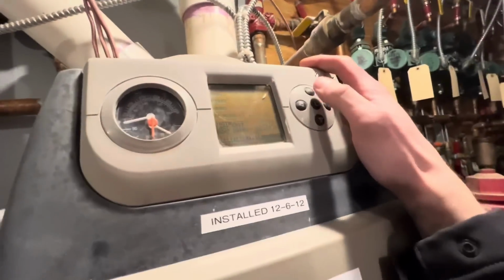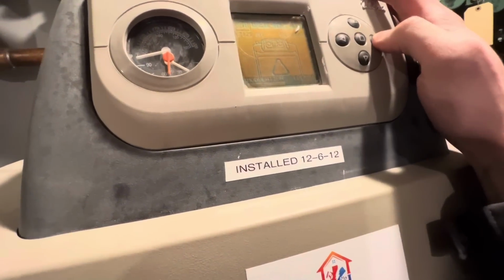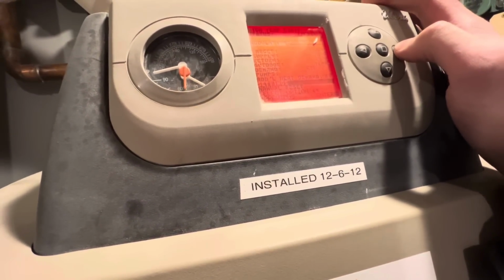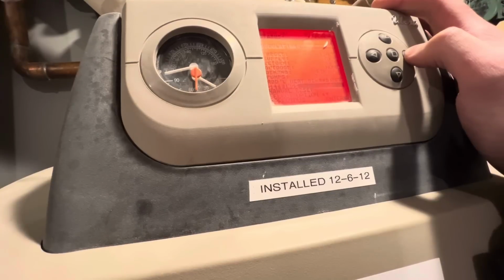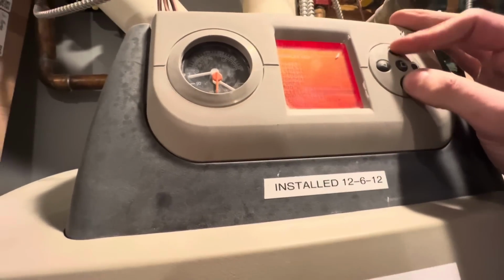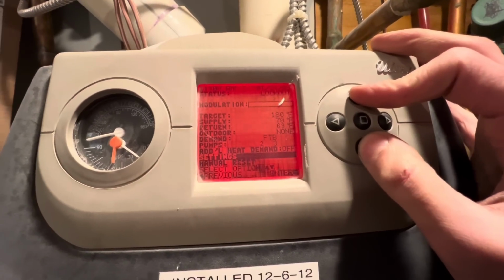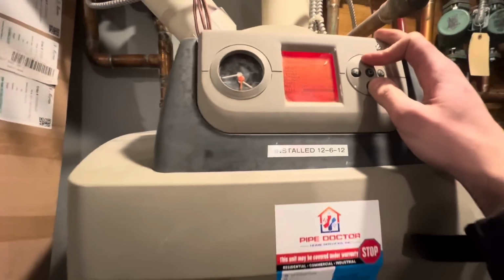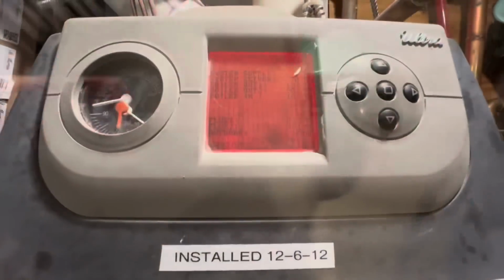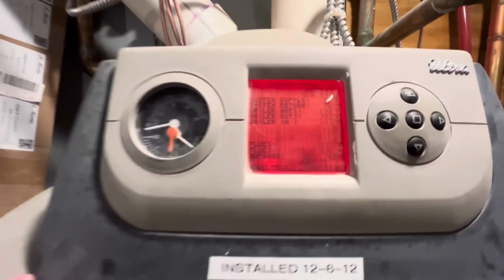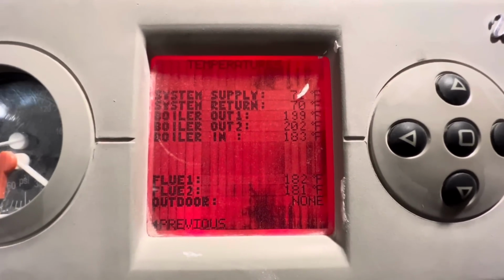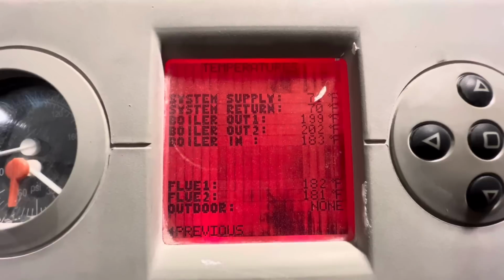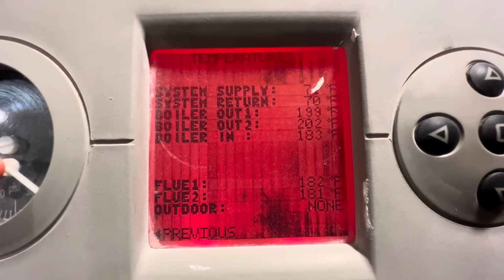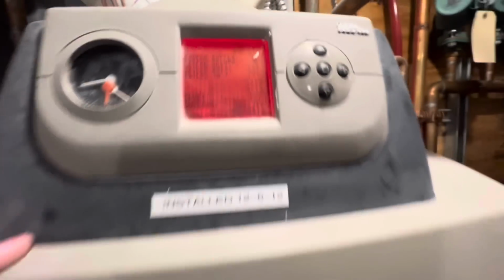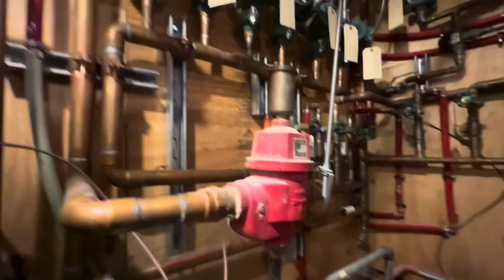Okay, so: maintenance reminder, lockout, high temperature limit. Let's see what's going on here. Get into contractor settings and go through everything. So if we look over here on our display, we had 202 on our boiler out, 199 on our boiler out, 183 on our boiler in, 70s on our system, which to me sounds like a circulation issue.